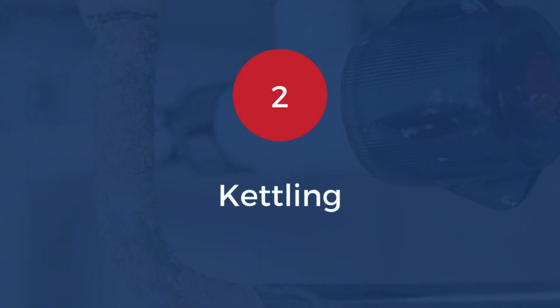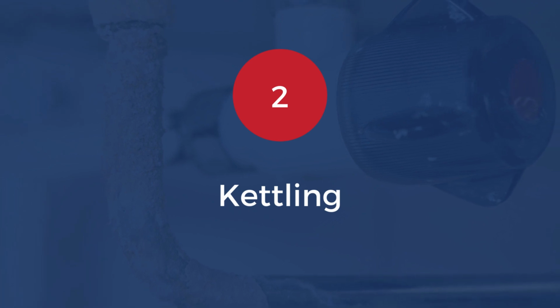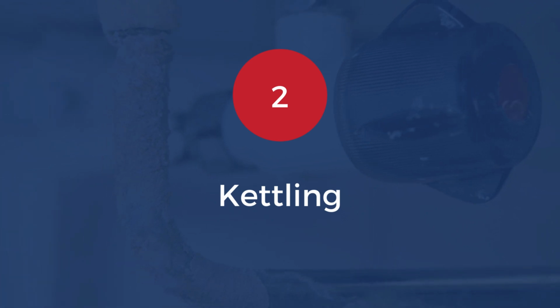2. Kettling. Lime, aka calcium buildup inside your boiler can be a problem over time. When buildup is excessive, it will inhibit water flow through the heat exchanger, causing the water to overheat and boil. When this happens, you'll hear a gurgling or rumbling sound, similar to that caused by a boiling tea kettle. A professional can solve your problem using a procedure called a power flush, which will dislodge sludge and/or calcium buildup if it is present. They will use specialized equipment to clean out your boiler system quickly and completely.